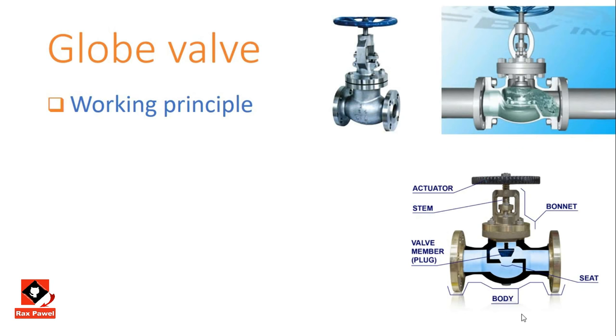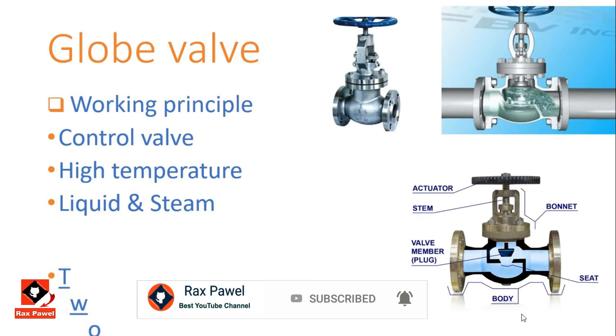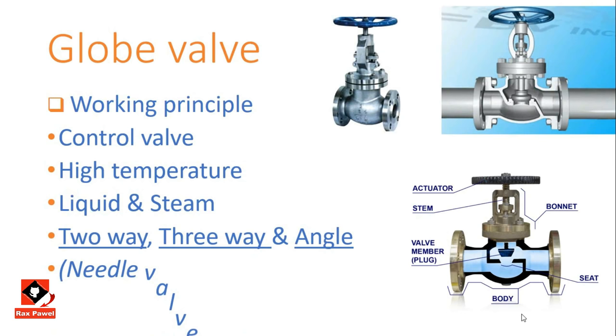Globe valve working principles: its stem is connected to a plug or disc which is moved perpendicular to the seat. The globe valve is common for throttling purposes and controlling high temperature applications, but can also be used as a shut-off valve. It is used for both liquids and gases. There are three types: two-way, three-way, and angle globe valves. The needle valve works on the same principle but uses a needle instead of a globe.